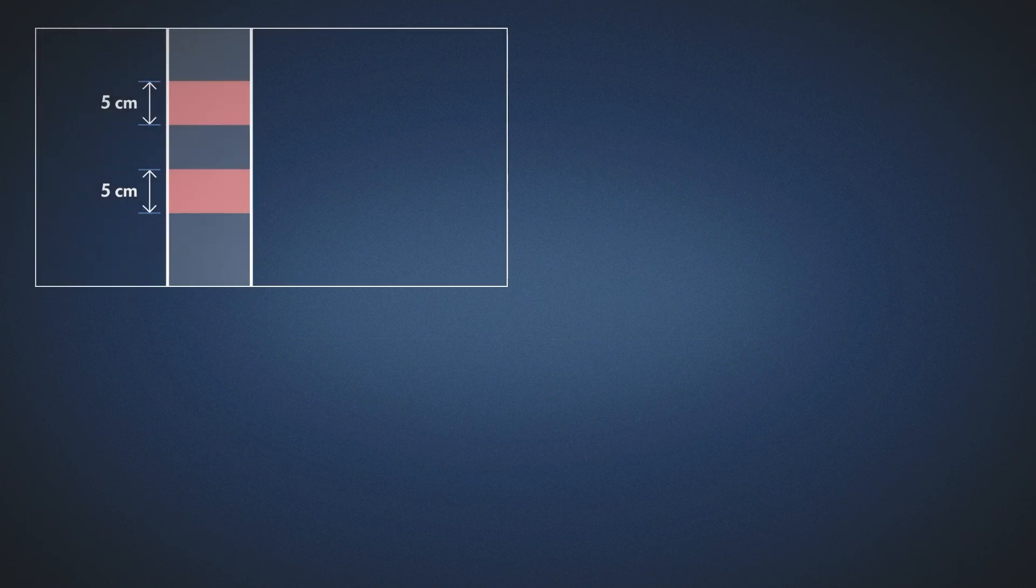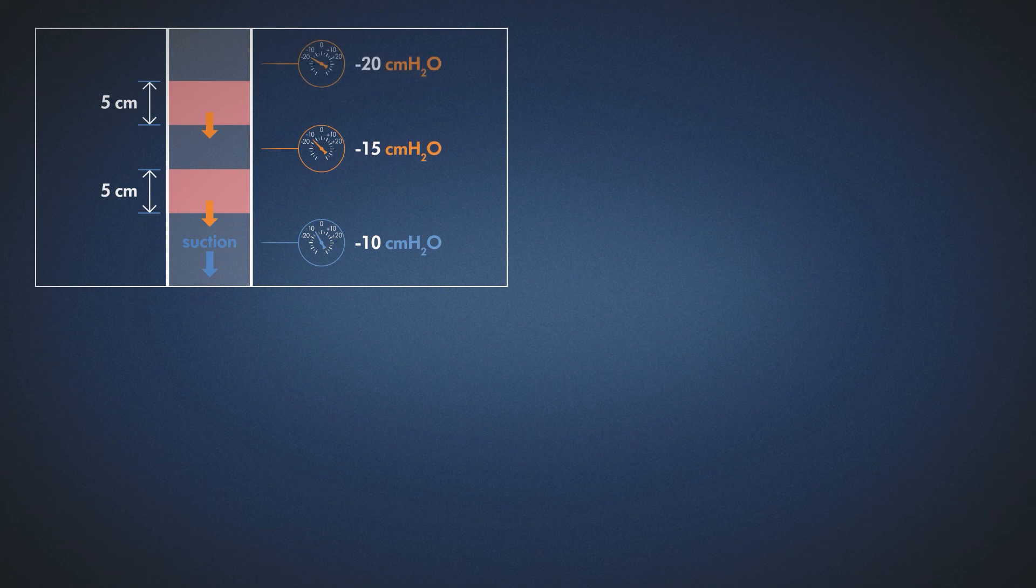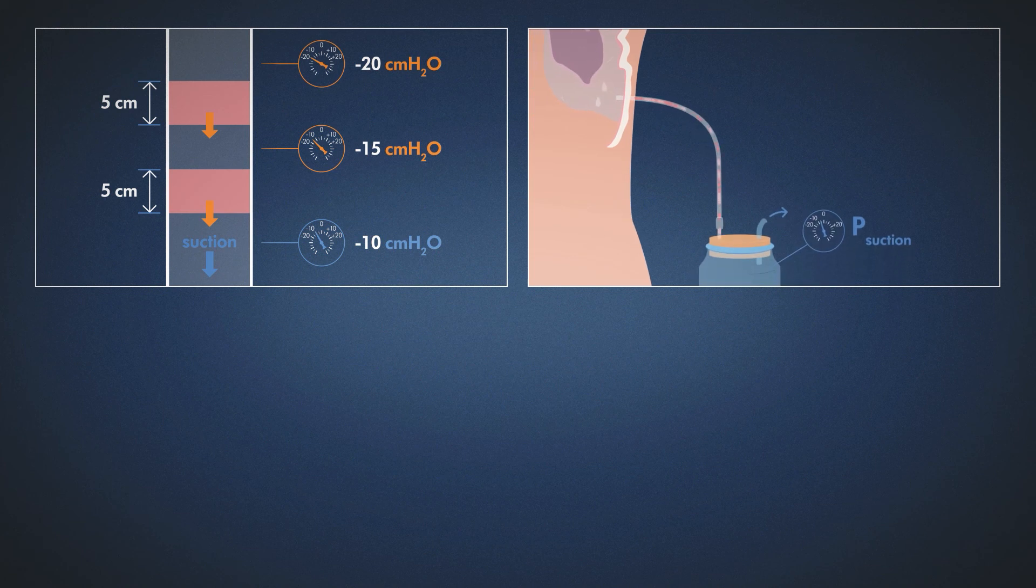Summary. Gravity acts on the fluid in a drainage tube and causes changes in the pressure at the patient's site relative to the suction set of the device. When the drainage tube is routed downward from the patient to the drainage device, the column of fluid in the tube causes a vacuum, which is added to the device's suction.